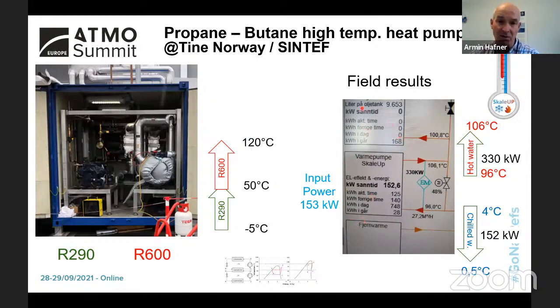Here on the right-hand side, I show you a field test or field result. The input power was about 153 kilowatt. The exit hot water capacity was 330 kilowatt, lifting the water from 96 to 106 in this case, while the chilled water came back to the system at 4 degrees and was supplied at 0.5 degrees, representing 152 kilowatt for this one single unit. And this dairy is very happy with this kind of system. So after this field trial, they will install more of them.